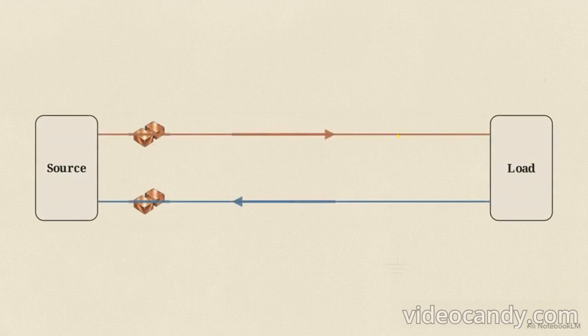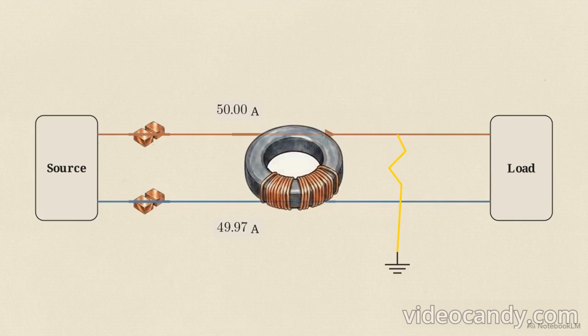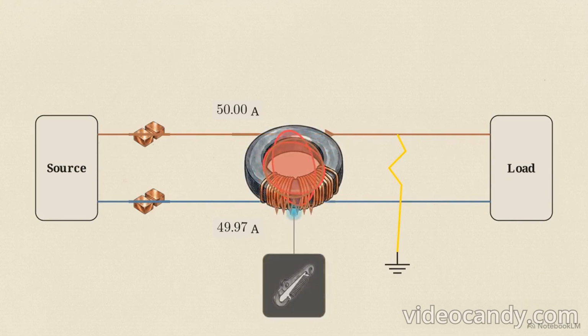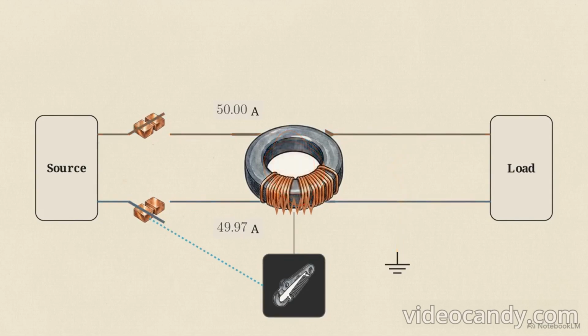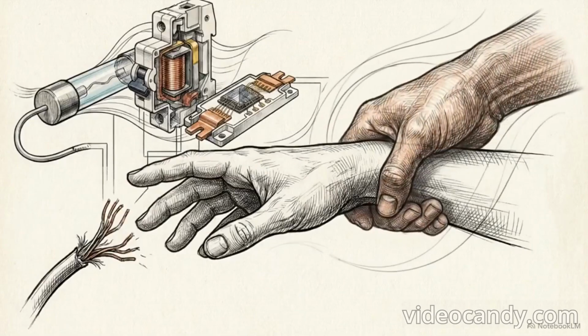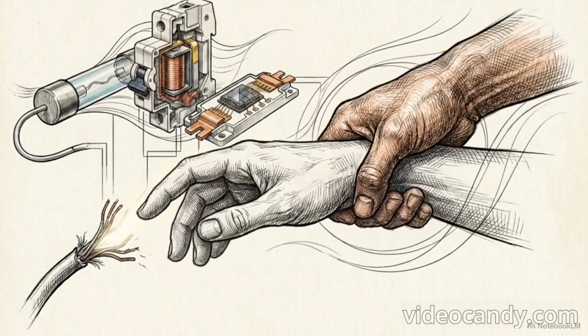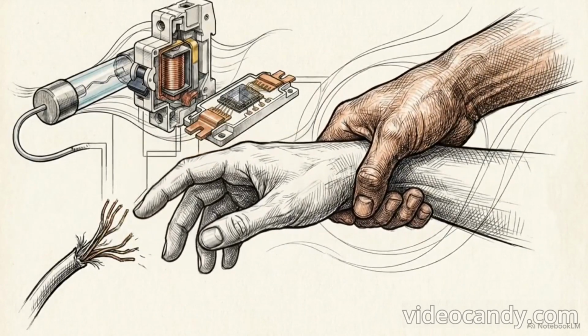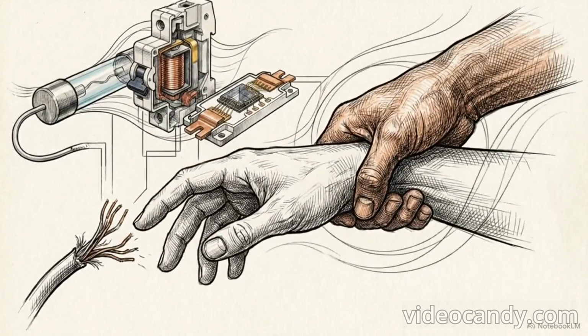Now introduce the fault. If a wire frays and current begins leaking to an earth ground or through a person, the math breaks. 50 amps leave on the line phase, but only 49.97 amps return on the neutral wire. This 30 milliamp vector imbalance leaves residual magnetic flux inside the toroid. That flux immediately induces a tiny voltage in a secondary winding coil wrapped around the ring. This induced voltage energizes a high-sensitivity relay, commanding the breaker to trip and sever the circuit. The RCCB intercepts lethal touch potentials exactly because it monitors mathematical flow rather than physical limits. It is a device built to prioritize human life.